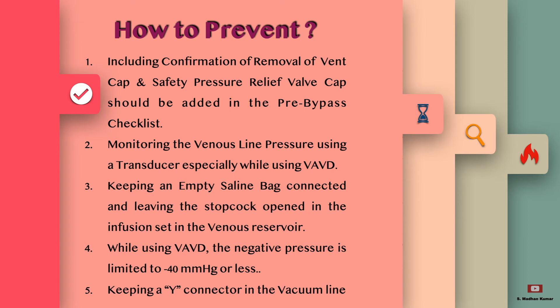Keep an empty cell-saver bag connected and leave the stopcock opened in the infusion set in the reservoir. When the venous reservoir is pressurized, it will bloat the empty bag, so that might be a visual confirmation for us. If we are not connecting a transducer while using VAVD, the negative pressure should be limited to minus 40 mmHg or lesser.